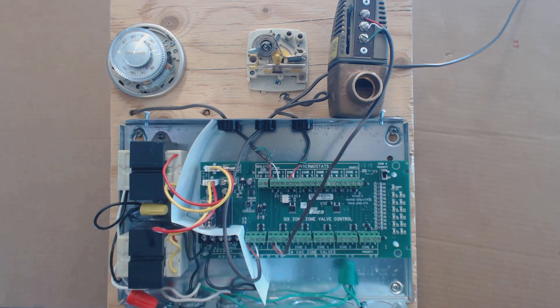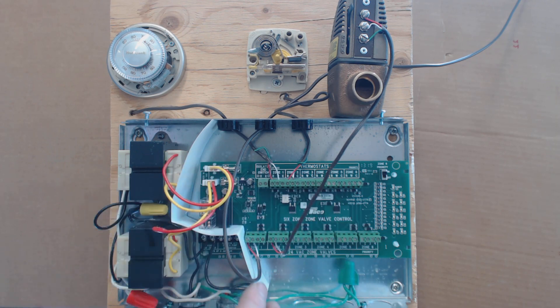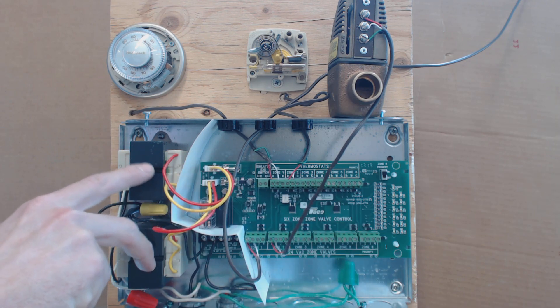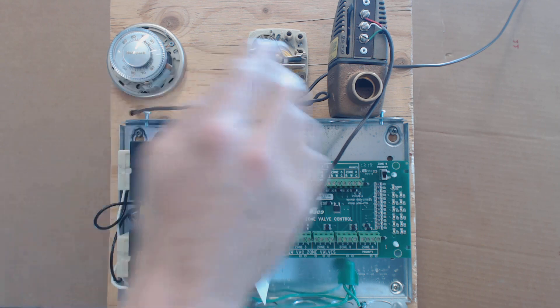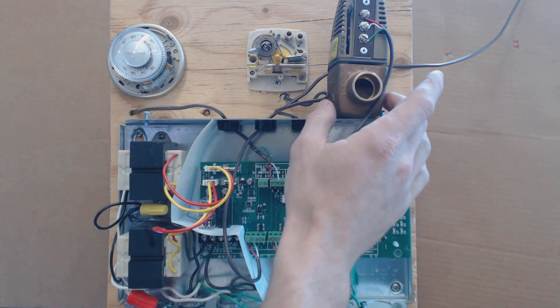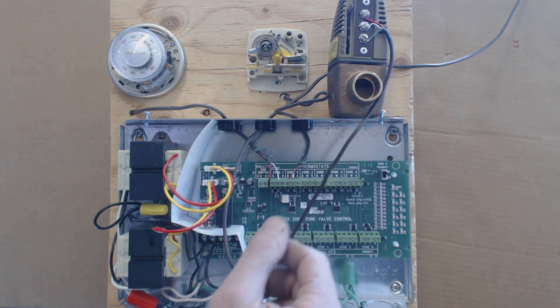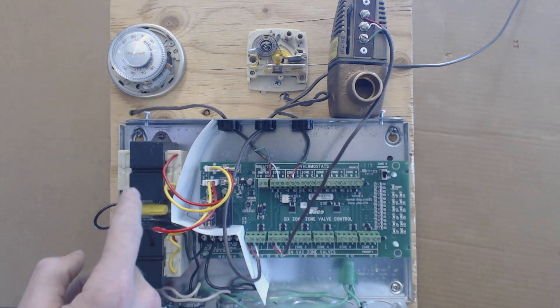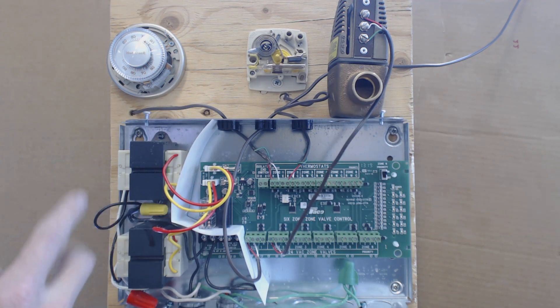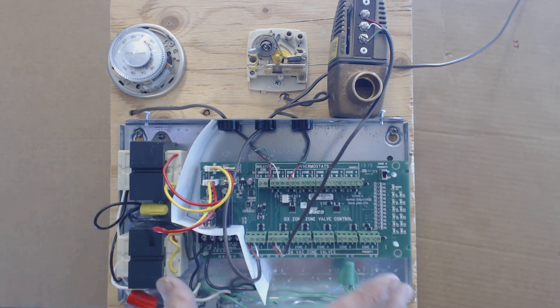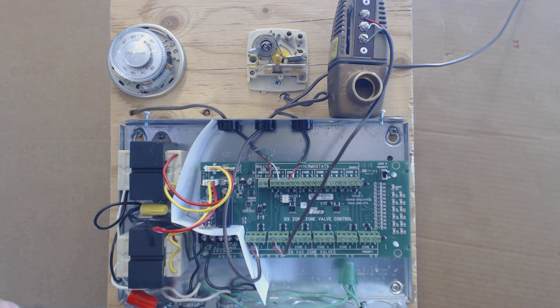So these can be used to power multiple zones, and it also gives you more transformer VA for your amperage for all these zone valves. These zone valves have been around for a long time. They are like 0.9 amps. They have more high-efficiency ones now that don't draw as much amperage, so you don't need as many or bigger VA transformers. But this allows you to kind of control everything in one six-zone valve control assembly. Hope you enjoyed yourself. This is AC Service Tech.